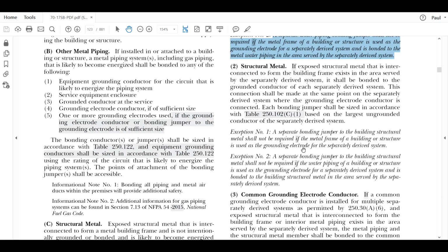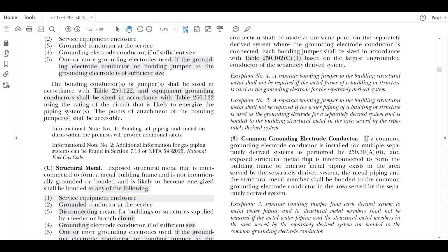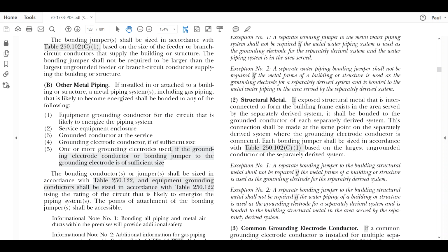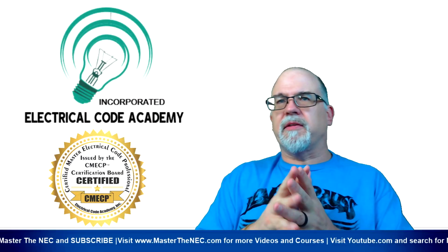The other exception here, these for the structural metal, it says a separate bonding jumper to the building structural metal shall not be required if the metal frame of the building or structure is used as a grounding electrode for the separately derived system. Okay, kind of the same concept, and it's no different down here. It's all the same. Okay. So that covers all of that, and you know what? That's all I'm going to cover for the basics.